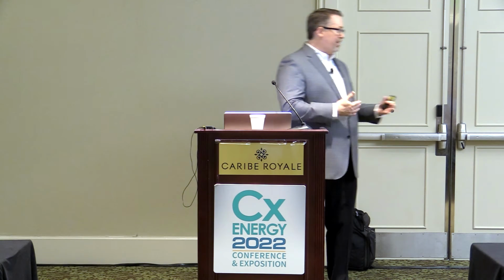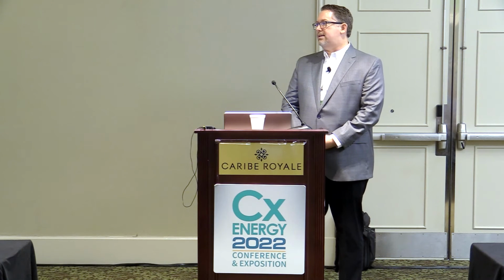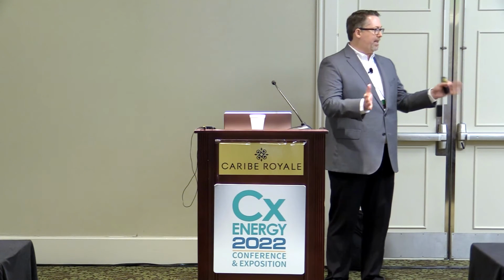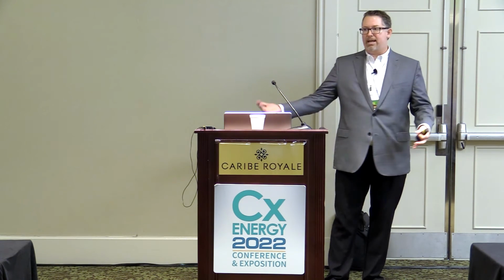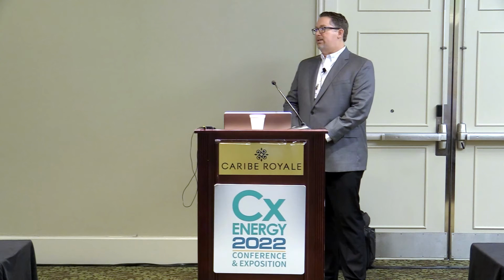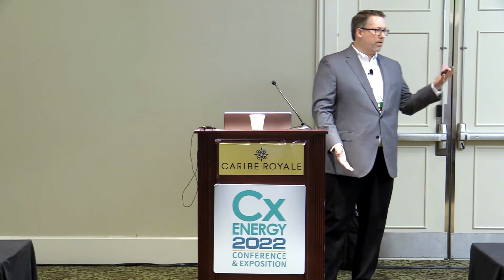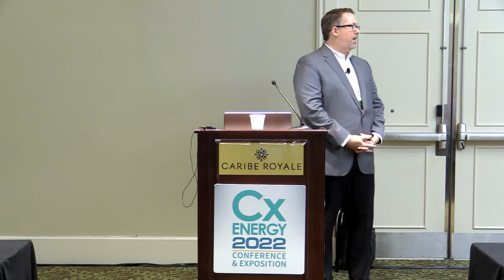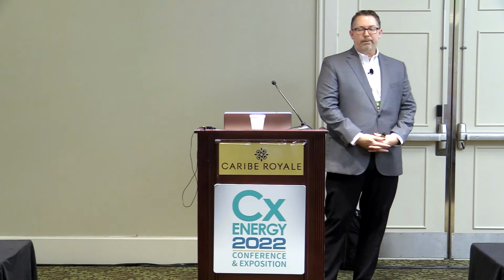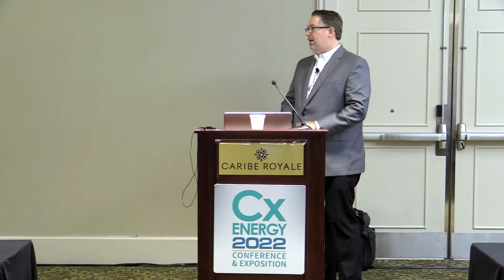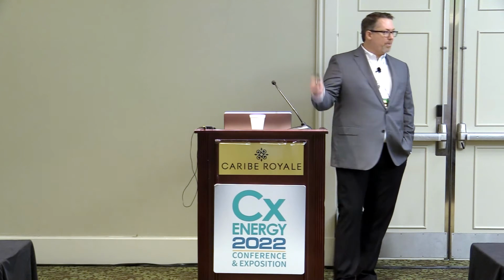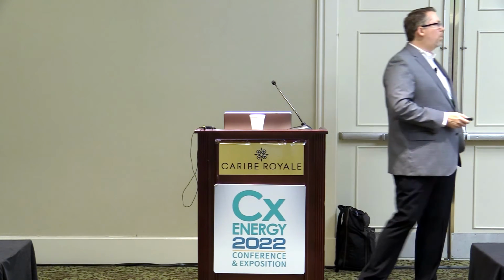Because of the potential issues, that one being a little more complicated and a little more time consuming, it's obviously balanced in a static condition when the building's not operating. But once that building starts to operate, there could potentially be issues with those differential pressures and the different demands, and we could see some problems there. We have pressure independent type that came out. We're starting to see thermostatic balancing valves used more and more.